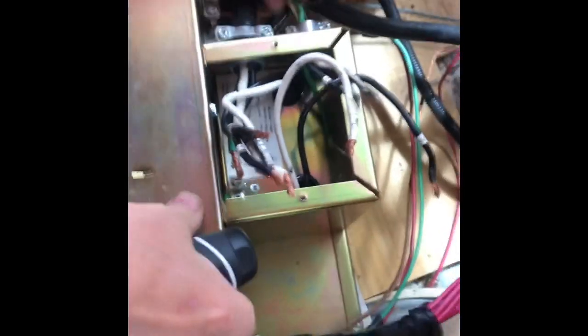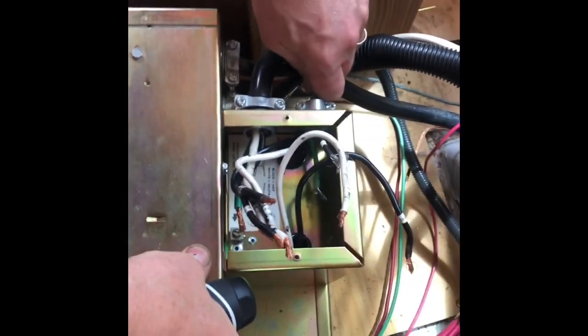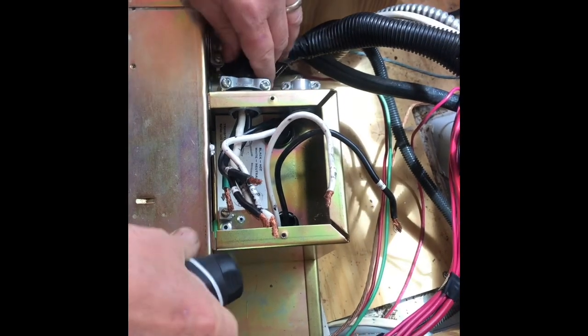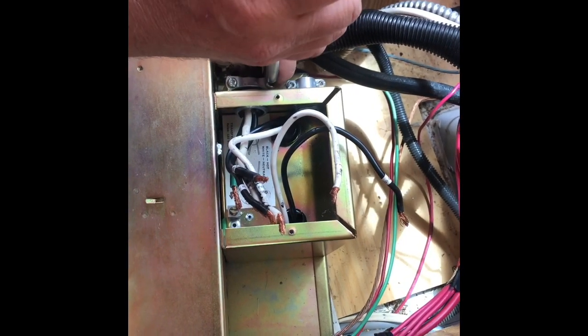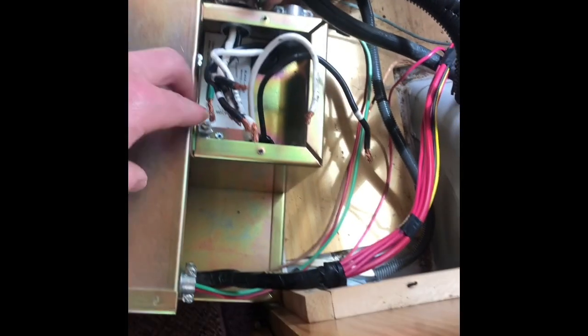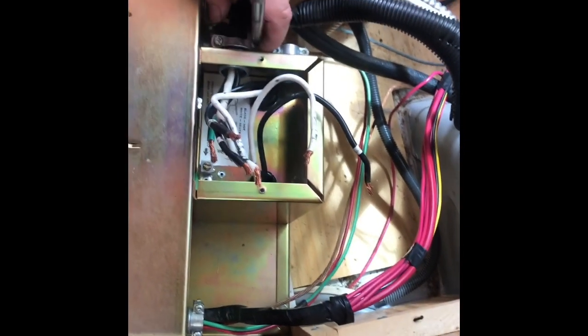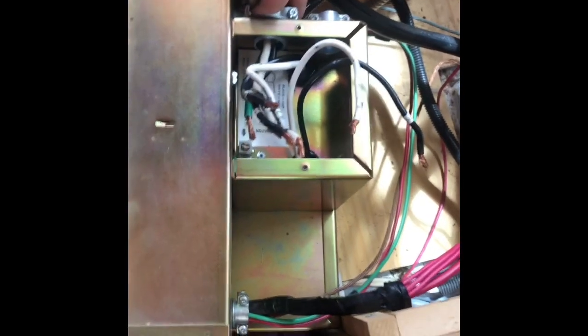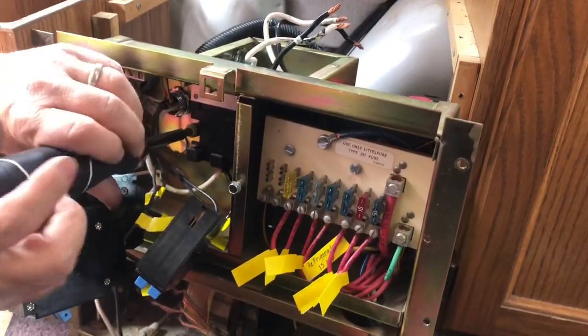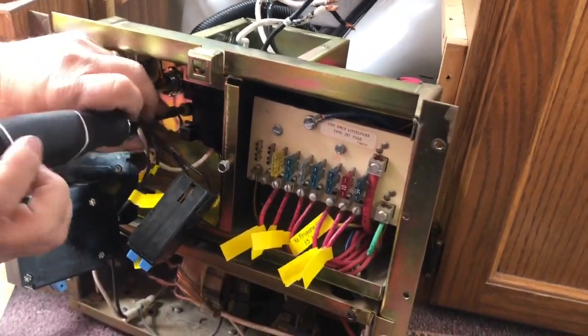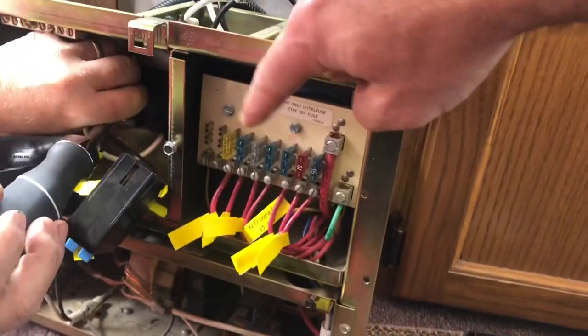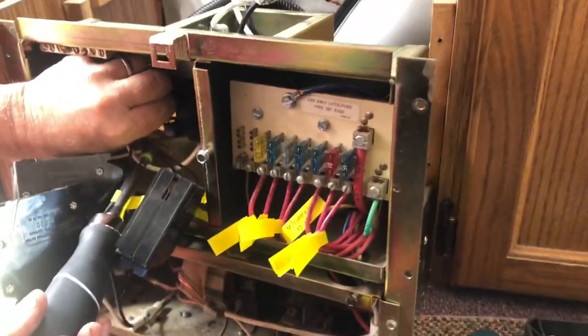We've got the wires all disconnected, we've got them labeled. Just pulling these out, you got the generator side out right there, and then you got the shore power on the other side. Just make sure you label where the grounds go and all the hots, so you can put them back together easily. So you got 2 bolts putting that automatic transfer switch on. There's one, and then the other one you need to remove the DC side panel to get at.